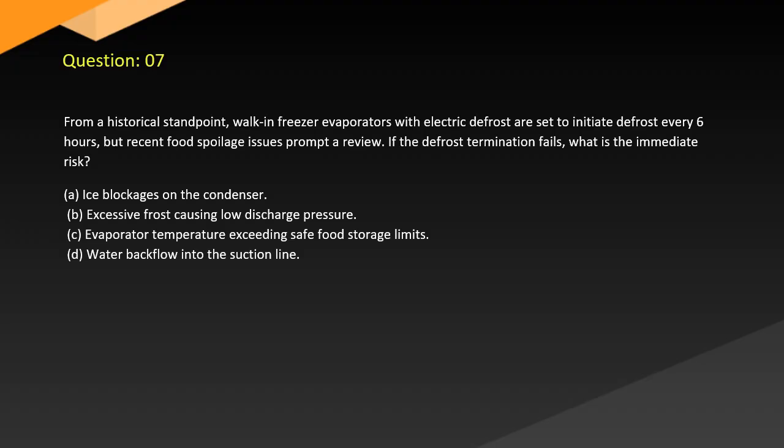Question 7. From a historical standpoint, walk-in freezer evaporators with electric defrost are set to initiate defrost every 6 hours, but recent food spoilage issues prompt a review. If the defrost termination fails, what is the immediate risk?